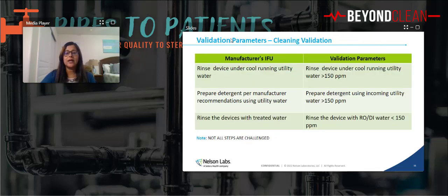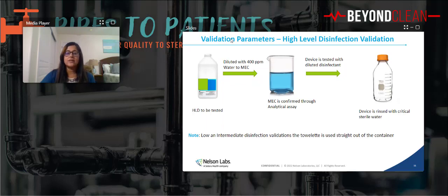This is just an example of a cleaning validation, manufacturer's instructions and validation parameters, giving you an idea of what we just talked about. Rinse under cool running water—we're doing it at greater than 150 ppm. Prepared detergent, greater than 150 ppm. And rinse devices in treated water, we're doing it less. Not all steps are challenged, but majority steps we do challenge. And we just talked about this for diluted disinfectants: 400 ppm, we dilute it, and then devices are rinsed with critical water. So only this step is affected, but the water system—we're still using the right water for rinsing.